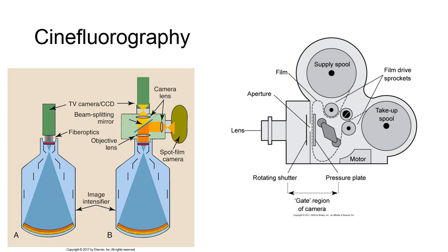To limit patient dose, automatic controls allow individual cineframe exposures only during instances of X-ray activation. Even taking this into account, patient exposure is typically relatively high using cinefluorography.